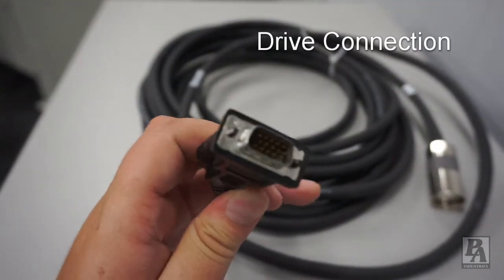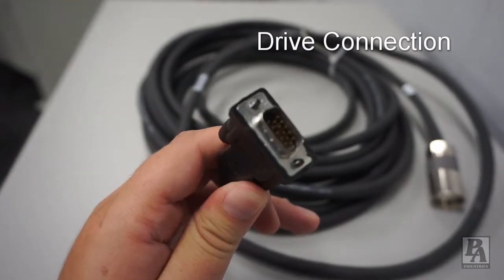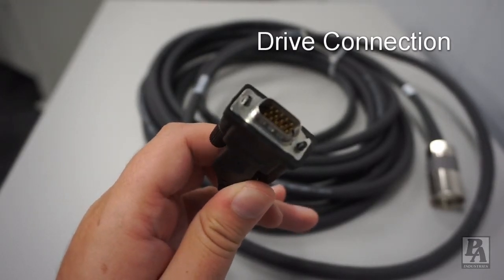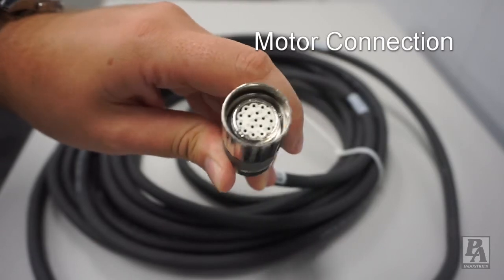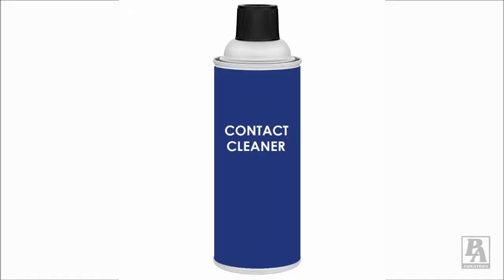Inspect the connection points. If any of the pins appear to be bent or broken, the cable will need to be replaced. If the pins appear to be undamaged, clean the connections using contact cleaner and reconnect.